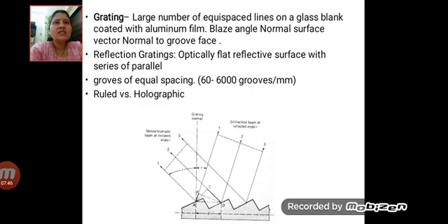The parallel lines or grooves are chemically etched on a thin layer of photoresist coated on a blank after exposure to interference fringes produced by the interaction of two beams of light from a laser. They can be used either as a transmission grating or, when aluminized, as a reflection grating. Rotation of the grating permits the appropriate wavelength of the spectrum to emerge from the exit slit of the monochromator.